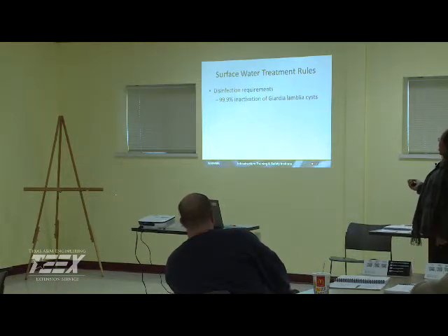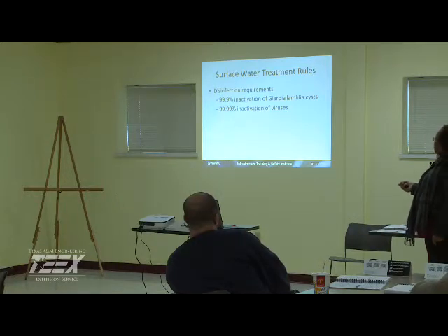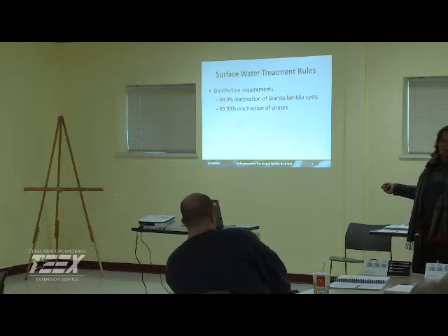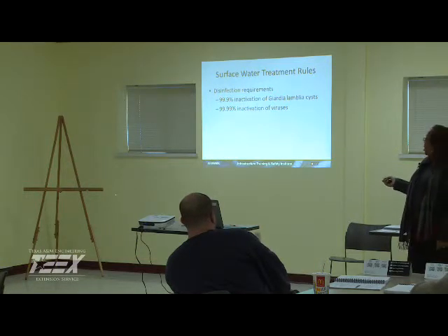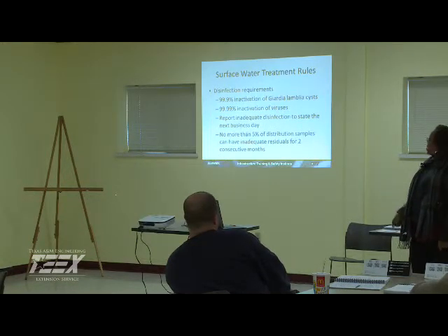Disinfection requirements under the surface water treatment rule: 99.9% inactivation of Giardia lamblia, that's 3 log, and 99.99%, that's the 4 log inactivation of viruses. Report inadequate disinfection to the state by the next business day, and not more than 5% of your distribution samples can have inadequate residual for 2 consecutive months.